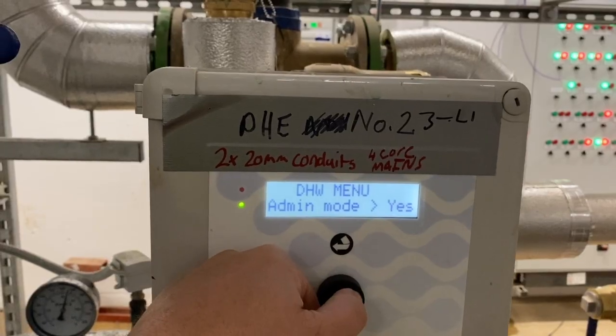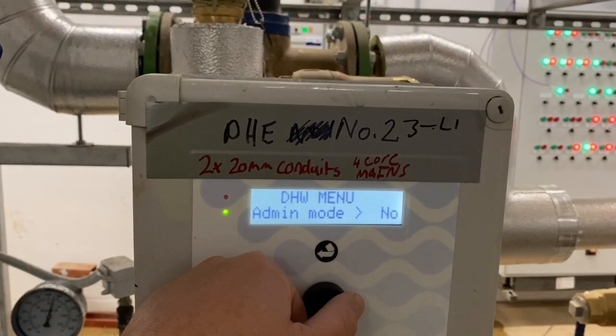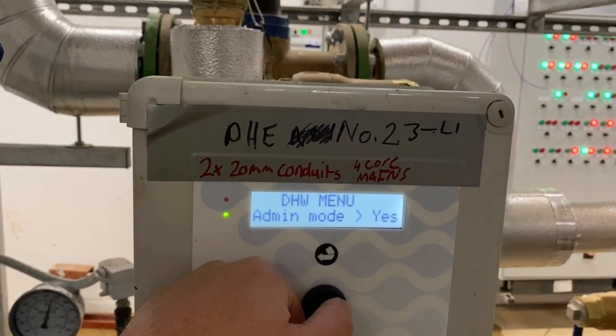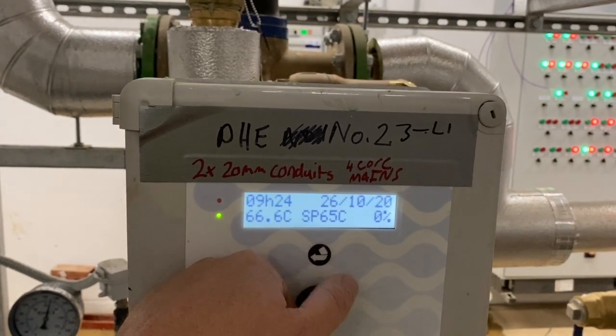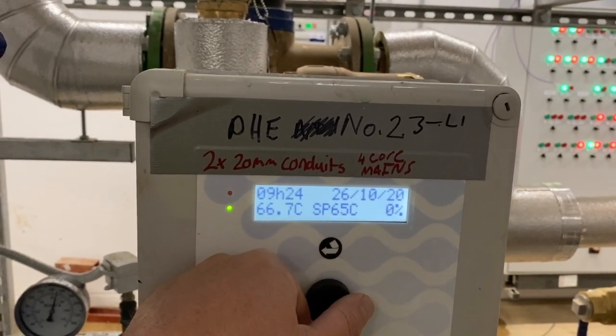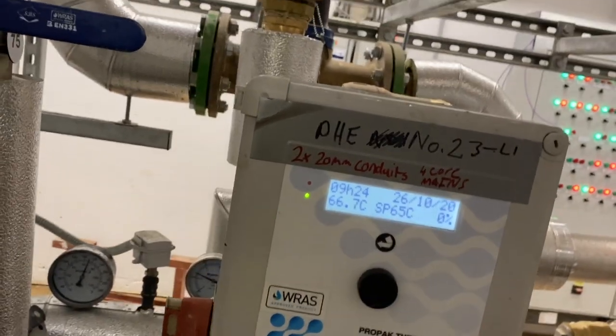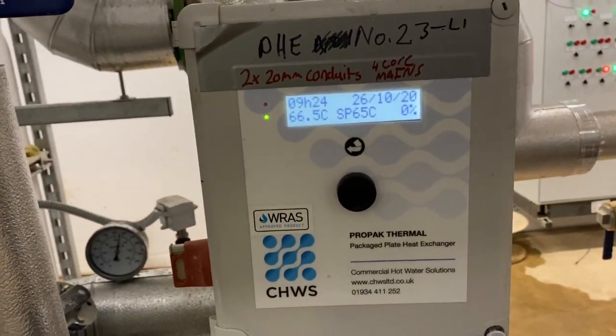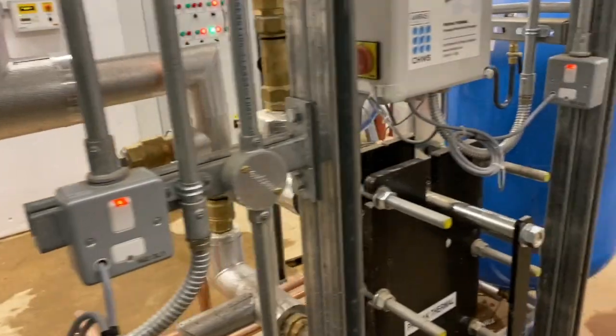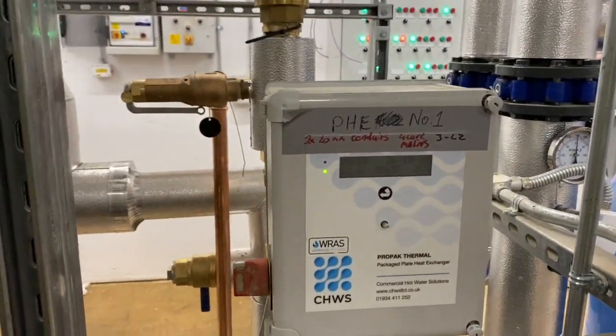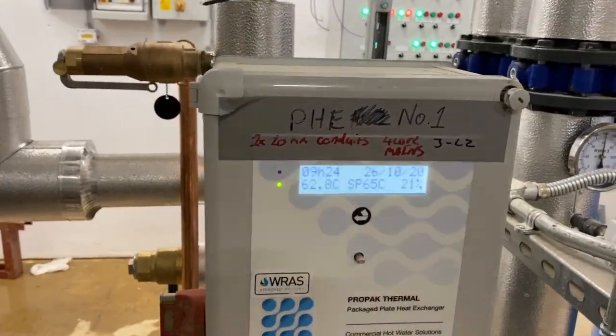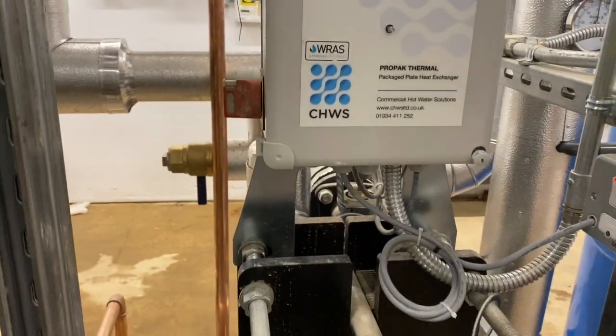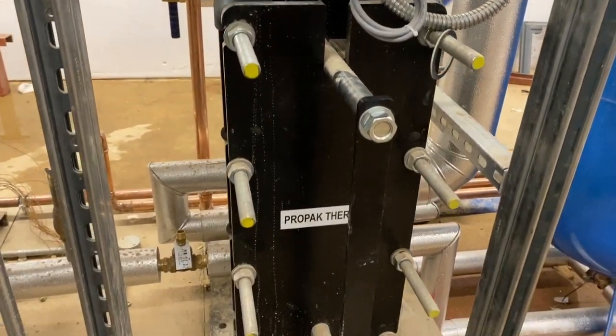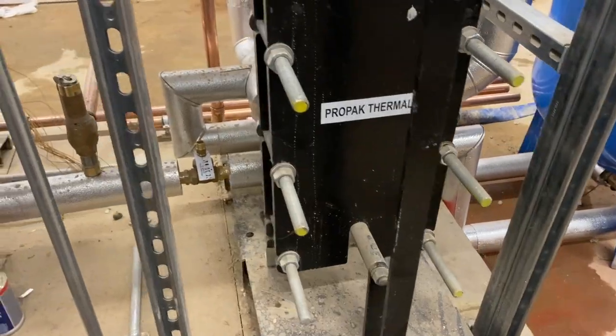Admin mode, this is where you need to go actually at the beginning to make sure you can change everything. All the way back. Now you see the display shows us the percentage of the 0%. It's showing us which position the three-way valve is going. Same again. Someone's stolen the knob on this one. But that's the plate and frame.